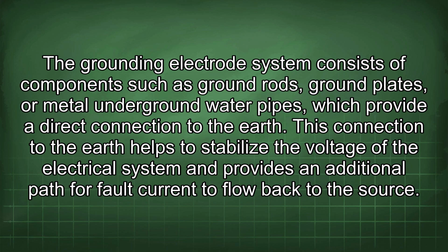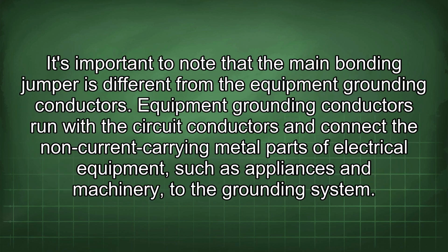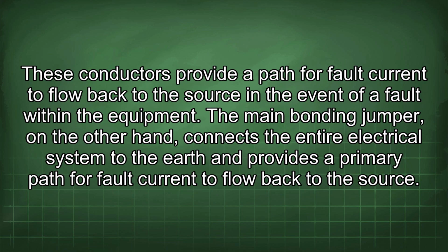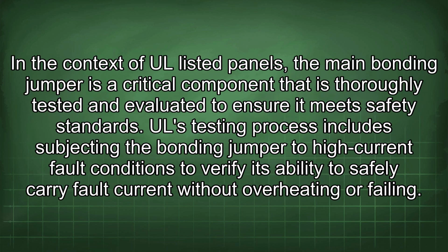This connection to the earth helps to stabilize the voltage of the electrical system and provides an additional path for fault current to flow back to the source. It's important to note that the main bonding jumper is different from the equipment grounding conductors. Equipment grounding conductors run with the circuit conductors and connect the non-current carrying metal parts of electrical equipment, such as appliances and machinery, to the grounding system. These conductors provide a path for fault current to flow back to the source in the event of a fault within the equipment. The main bonding jumper, on the other hand, connects the entire electrical system to the earth and provides a primary path for fault current to flow back to the source. In the context of UL-listed panels, the main bonding jumper is a critical component that is thoroughly tested and evaluated to ensure it meets safety standards.